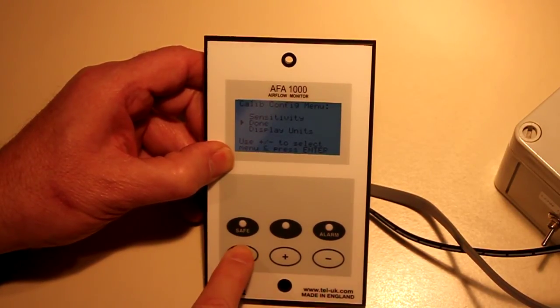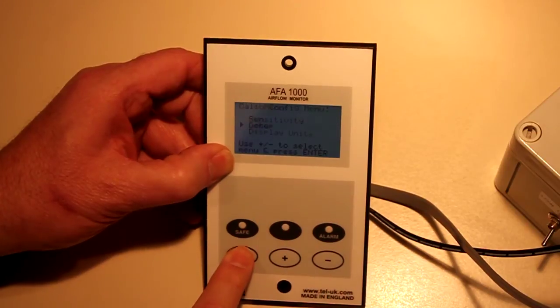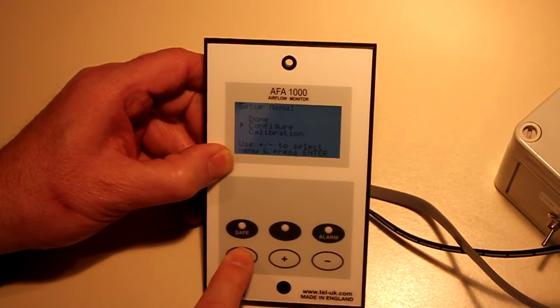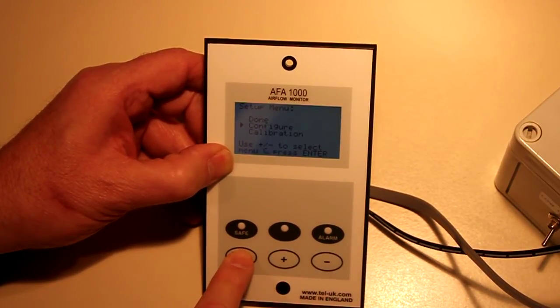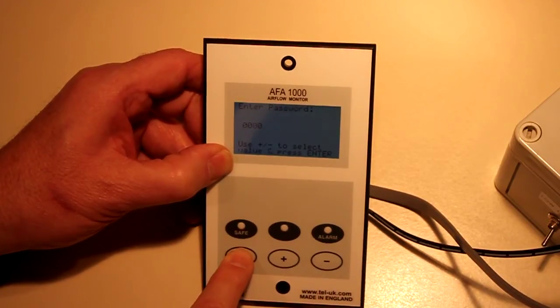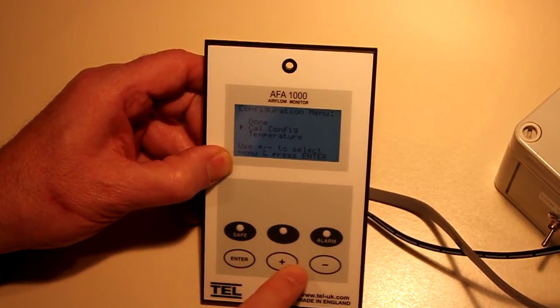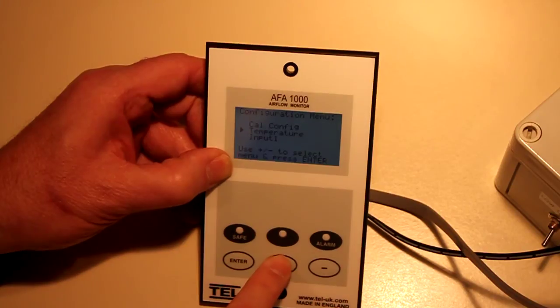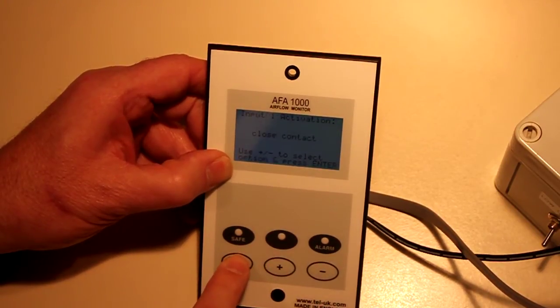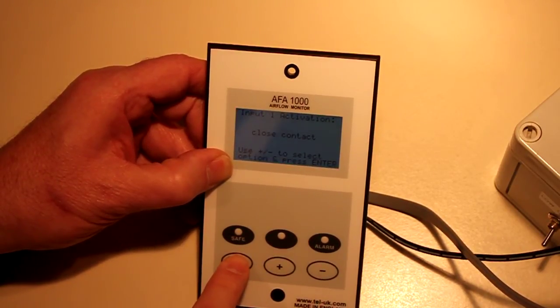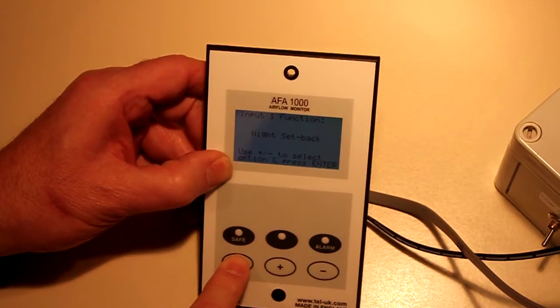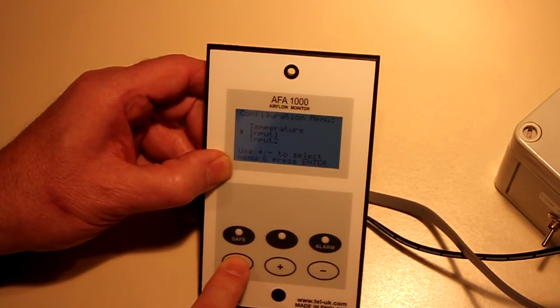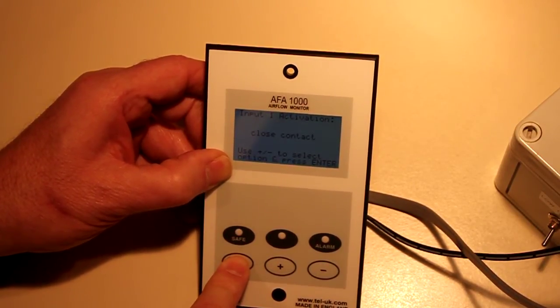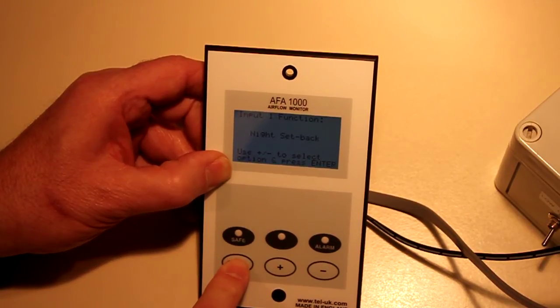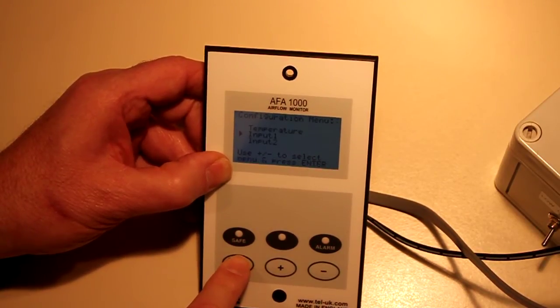The 3 relay outputs are used to send a signal to another monitor or external device to indicate the airflow status of the hood. The AFA 1000 has a 0 to 10 volt output port sending an electrical signal based on the measured velocity and scaled over a range of 0 to 200 feet per minute, equivalent to 0 to 10 volts. In the event of an air fail alarm, pressing the Enter button once will silence the horn until the sensor sees enough airflow to return to safe mode.